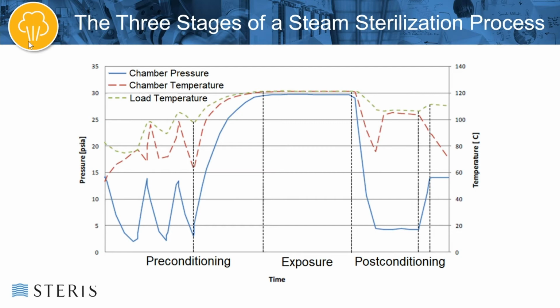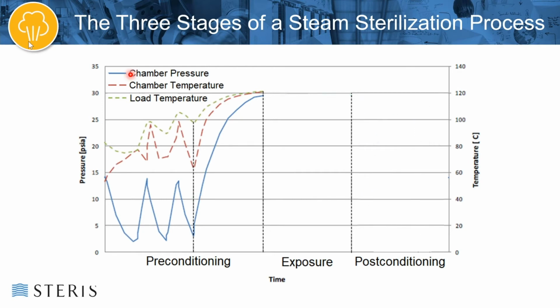So with regard to actual steam sterilization processes, there are essentially three stages: preconditioning, exposure, and then post-conditioning. You can see by this chart that we have pressure on the left side, time on the bottom, and temperature on the right. Let's talk first about the preconditioning phase. The blue line represents chamber pressure, the red dotted line is chamber temperature, and the green dotted line is load temperature. This preconditioning phase is essentially broken into two steps.